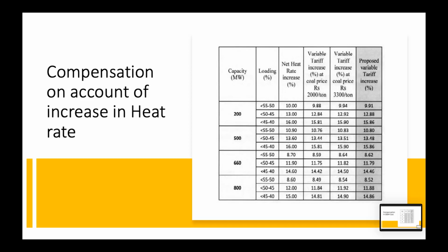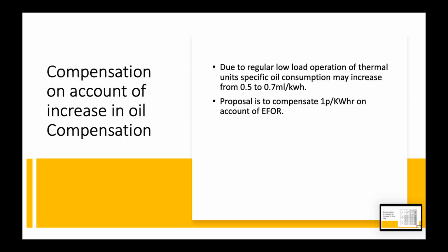Now we will talk about the last compensation which the CEA has talked about, that is on account of oil consumption. Presently, the norm is 0.5 ml per kilowatt hour for a thermal power plant, and it has been proposed that during regular low load operation, the specific oil consumption may increase, and it may go up to 0.7 ml per kilowatt hour. So they are planning to increase the limit also.